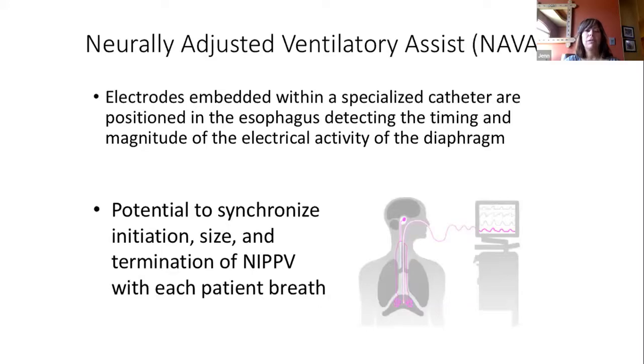And then lastly, I want to talk about neurally adjusted ventilatory assist, or NAVA. And what this is, you can see the little picture showing you that this is an electrode that's embedded in a special catheter positioned in the esophagus down by the diaphragm. And what this does is it detects electrical activity, timing, and magnitude of this activity in the diaphragm, so that it can then synchronize the breath that the vent's giving, and you can synchronize initiation of the breath, the size of the breath, and termination of the breath with each patient breath. So this is a really new and exciting mode of ventilation that we have.